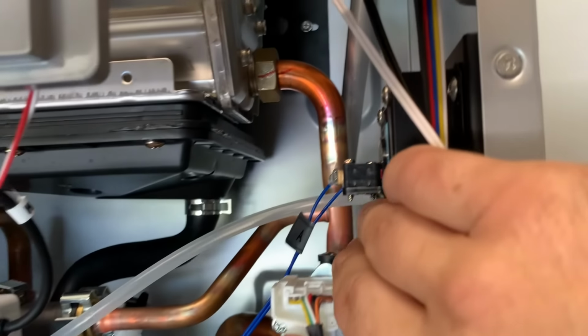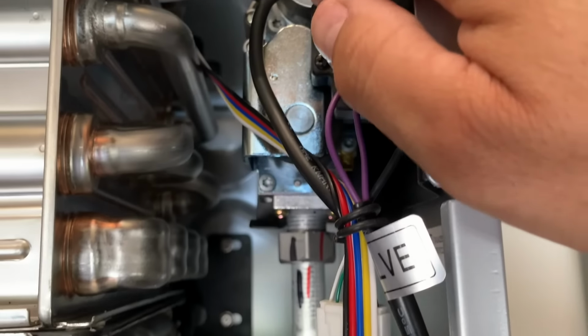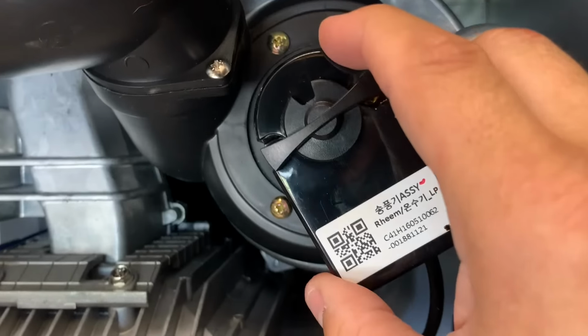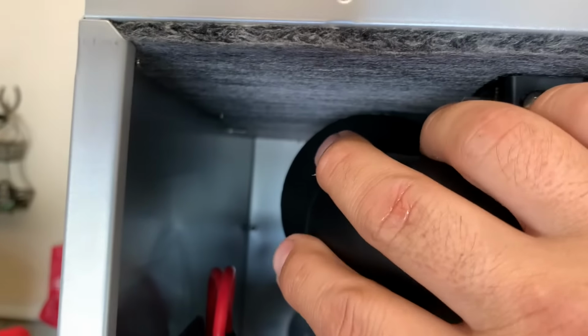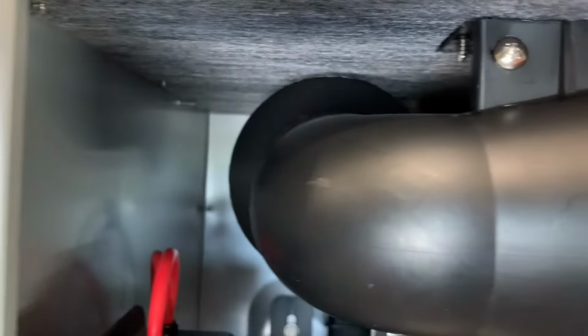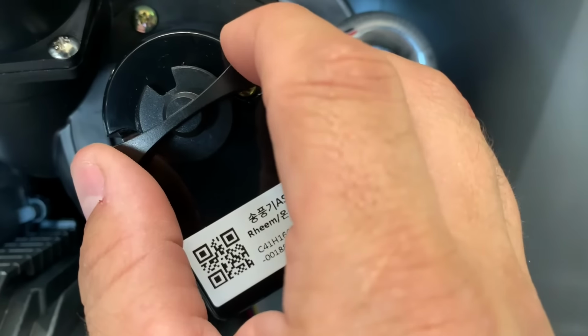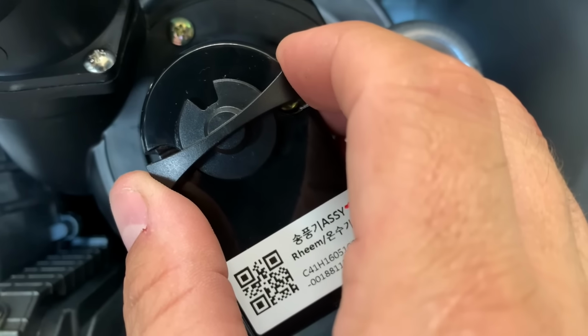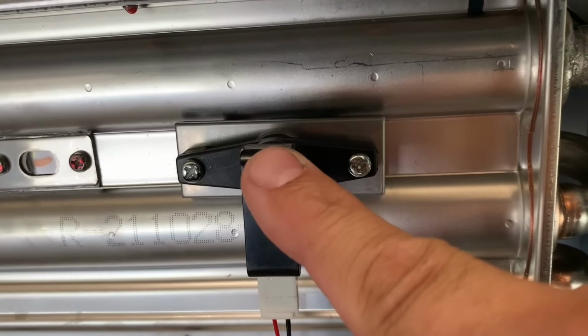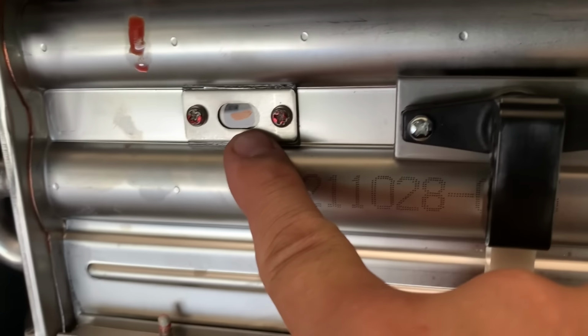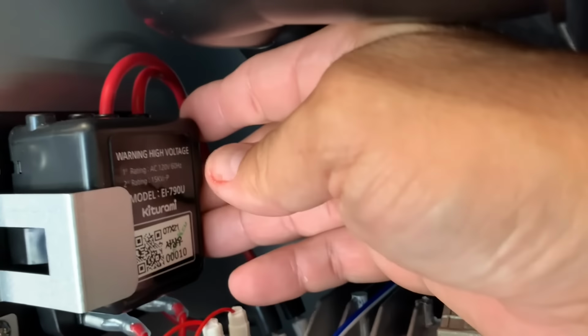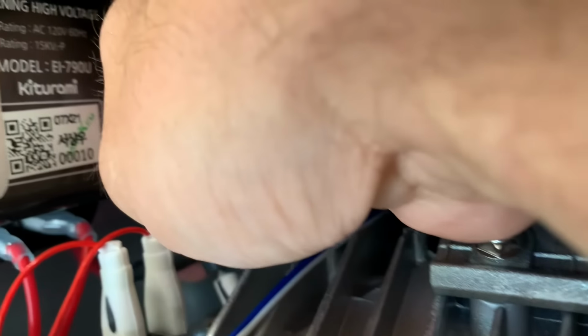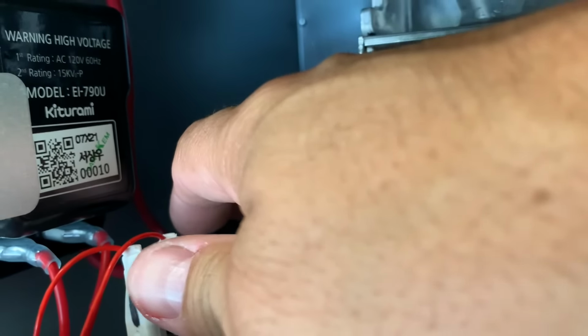Moving up through here, you have an air pressure switch, gas control valve, blower motor, air intake that's horned at the end, presumably to help with any noise. This will regulate airflow as the water heater is running. Optical sensor, sight glass. Up here you have your transformer, or I call it a coil. It's going to deliver spark to your igniters. There's 2 of them. You can test these by holding a wire off and out towards some metal. When I did that, it did shock me. There are 2 igniters. If one has failed and one is getting spark, it will still work.